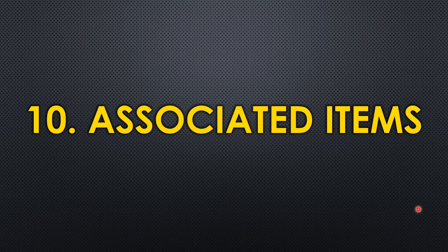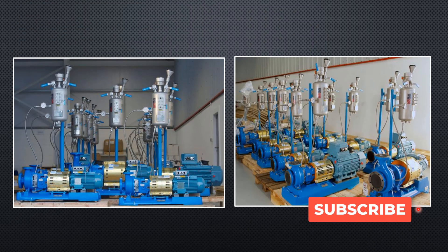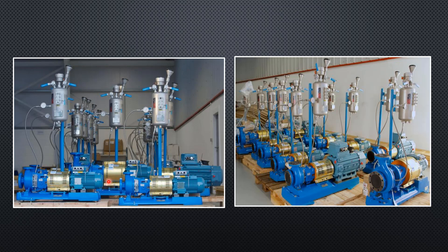The tenth parameter is associated items. A pump does not come alone — it includes a motor, a seal pot, panels, junction boxes, vibration monitors, and many other components. The pump comes as a package. You must study all associated items before planning the piping. If you ignore the seal pot, for example, you may end up routing piping that clashes with it and have to re-route. Knowing the full package allows you to design pump piping that won't need rework when the vendor package is finalized.